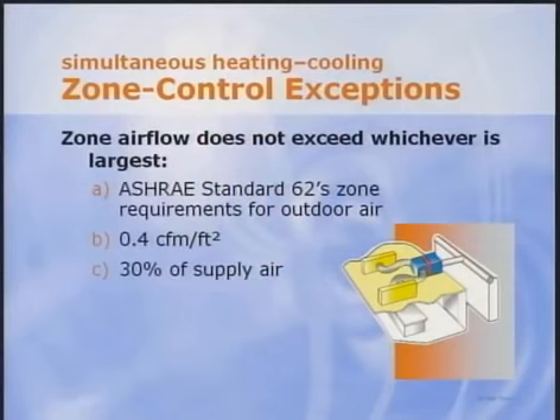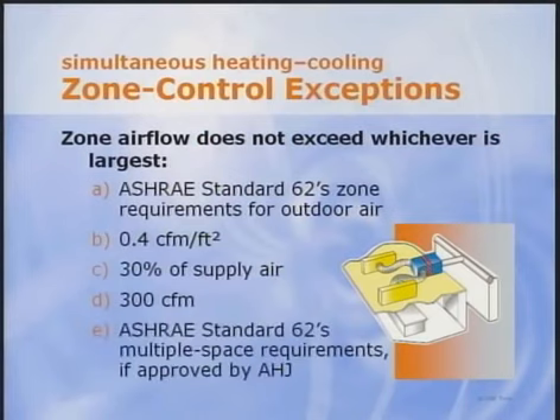We don't see the exception for 300 CFM used too often, except perhaps on small zones. And finally, exception E allows us to use the ASHRAE 62.1 multiple zone system equations and set the minimum airflow higher in potentially critical zones as long as the overall system energy usage goes down. We've communicated with other engineers who think this is a tough one to use because it must be approved by the authority having jurisdiction. Later, Steve will share some experiences using this method.